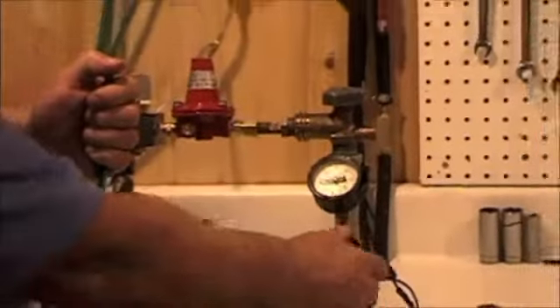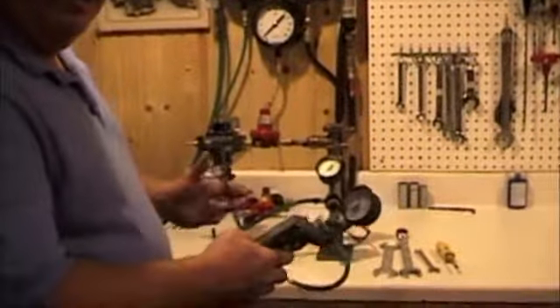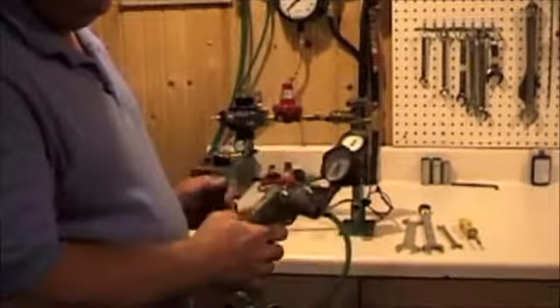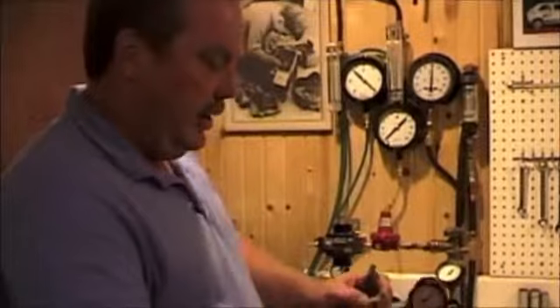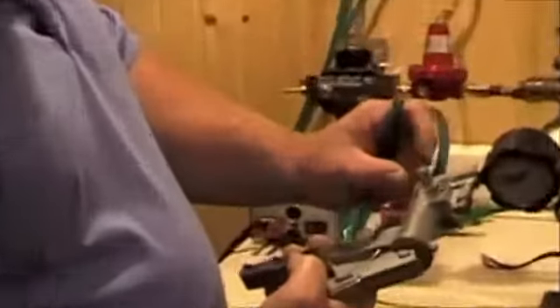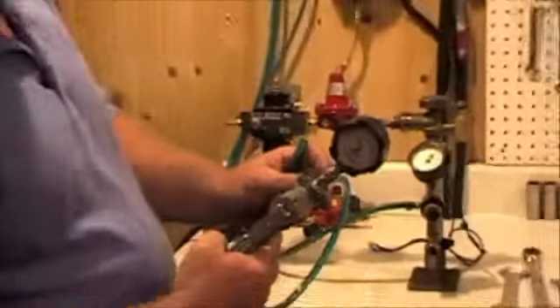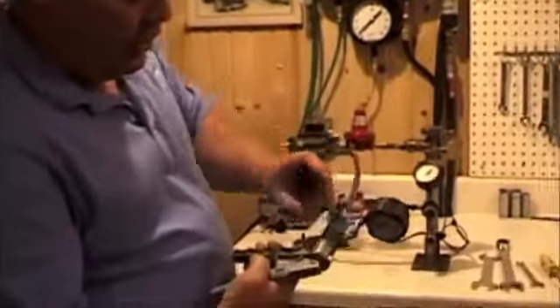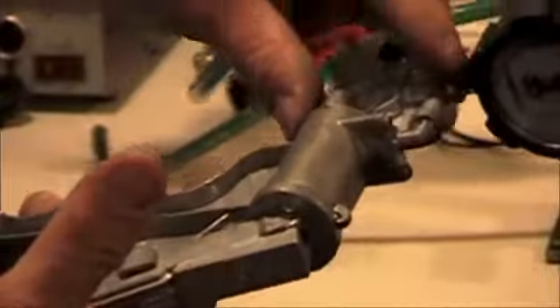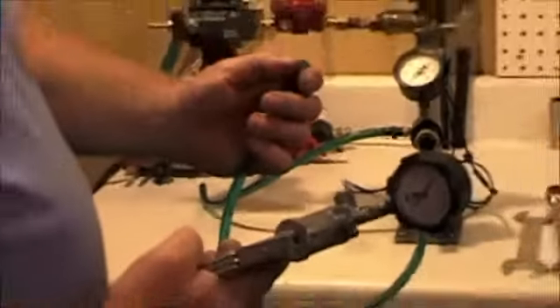I can do it with this device, which we use for calibrating lots of units, or in the field we like to use a handheld Mityvac pump. Now this is a pressure and a vacuum pump. It has a switch on the side of it to go from vacuum to pressure. Not all of these have this. This end that comes with a Mityvac pump is a separate piece that you can purchase from Mityvac or through your auto parts store.